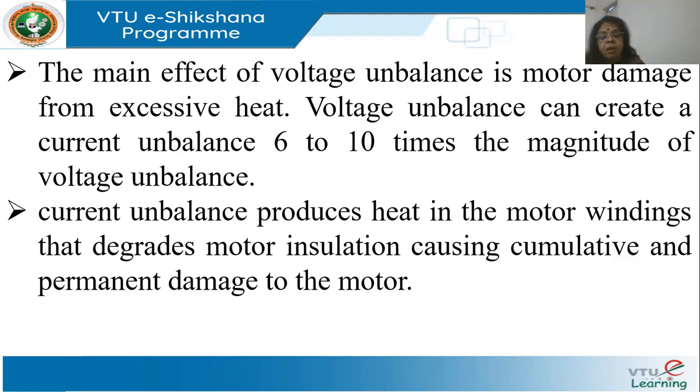Negative sequence currents will also produce excessive heat in the motor. The temperature rise of the motor is directly proportional. So we cannot allow very large negative sequence component currents in the motor. This heat will degrade the motor insulation and cause permanent damage to the motor. And we are not talking of small motors. We are talking of huge drives, so it can lead to heavy losses to the industry.